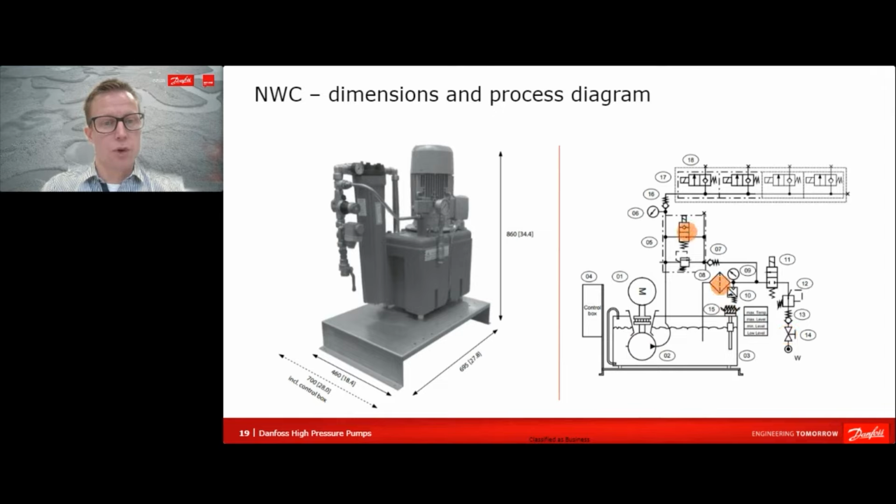And up here you have your power pack valve, meaning that when there's no need for flow out here in your application, or at least not as much flow as the pump is providing, it will be relieved here via the relief valve as part of the power pack valve. Or you can simply also open the VDHT valve, or the solenoid valve, which is also part of the power pack valve here, and then run pressure-free, directly circulating the water back to the tank in case all the valves here in the application are closed.